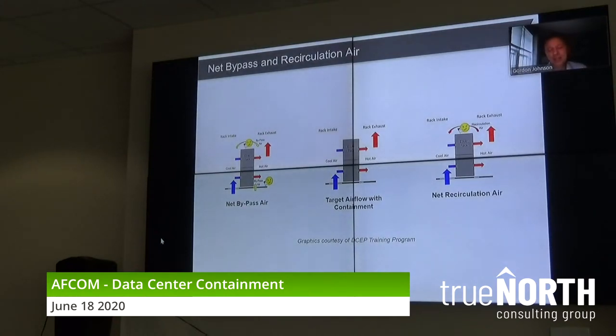And you'll hear a lot of people say, hey, the hotter the air being returned to your CRAC units, the more cooling you'll get from the CRAC, that's true. The more efficient that CRAC will run. Those are all true. We won't get into that now, but I want those hot temperatures back at my CRAC.